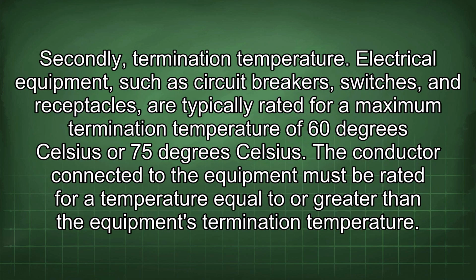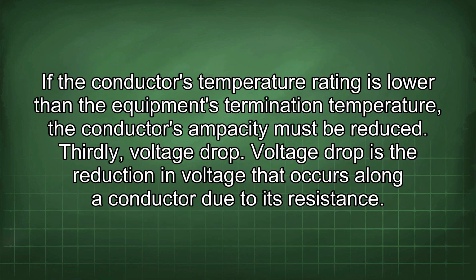Secondly, termination temperature. Electrical equipment, such as circuit breakers, switches, and receptacles, are typically rated for a maximum termination temperature of 60 degrees Celsius or 75 degrees Celsius. The conductor connected to the equipment must be rated for a temperature equal to or greater than the equipment's termination temperature. If the conductor's temperature rating is lower than the equipment's termination temperature, the conductor's ampacity must be reduced.